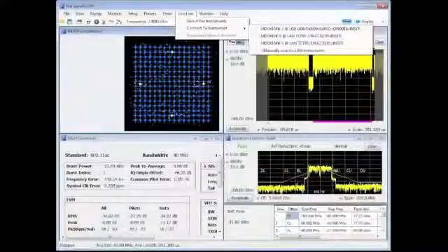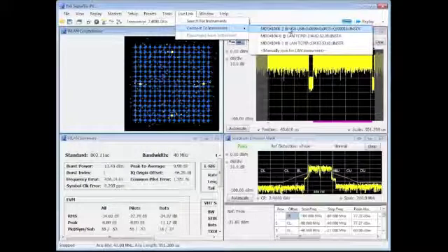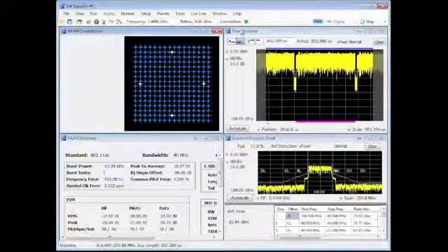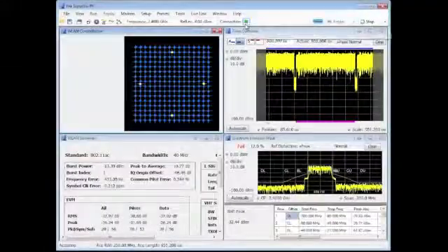It goes out, it scans the network, it scans USB, it scans GPIB if you've got a card. And then it populates this menu with all the instruments that it found. So we're going to pick our USB instrument. There it is, showing up easily. We get a confirmation. And now our display is updating live with the data that it's grabbing from the MDO4000B. Just as easy as that. And if we want more information about the connection, we can hover over this little link here.